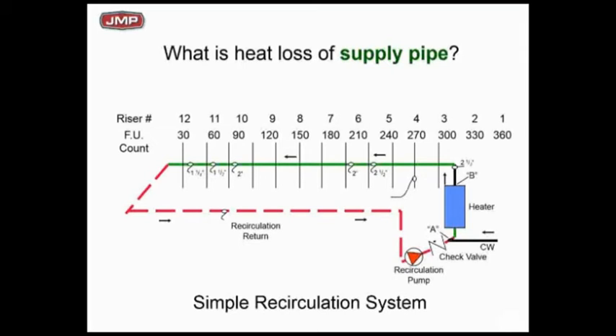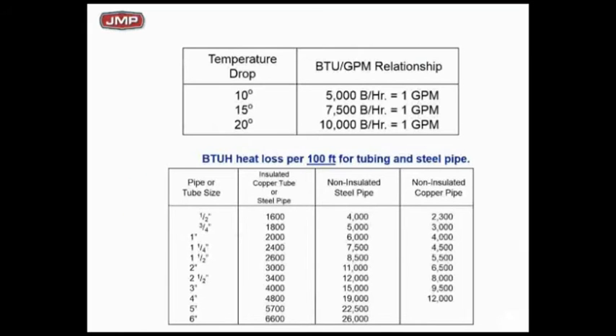Let's look at the simple recirculation system we reviewed earlier with 300 feet of pipe. B&G put together a quick chart: with a 10-degree delta T, one GPM will allow you to offset 5,000 BTUs. With a 20-degree delta T, one GPM offsets 10,000 BTUs. In other words, if my heat loss in a piece of pipe is 10,000 BTUs, I could flow one GPM through it at a 20-degree delta T, or two GPM at a 10-degree drop. This is a quick tabular method for calculating the GPM required to offset heat loss in the supply pipe.